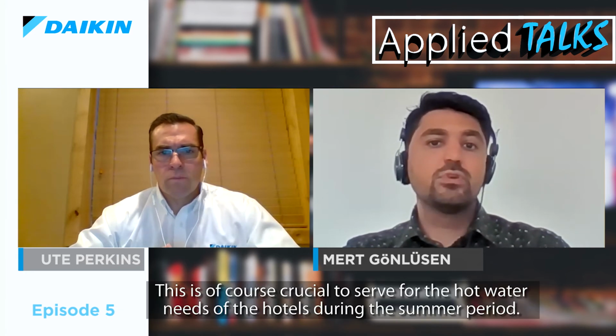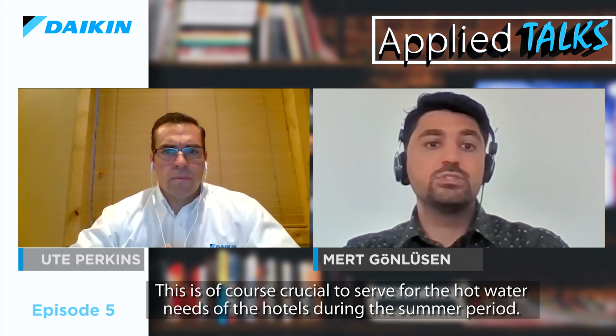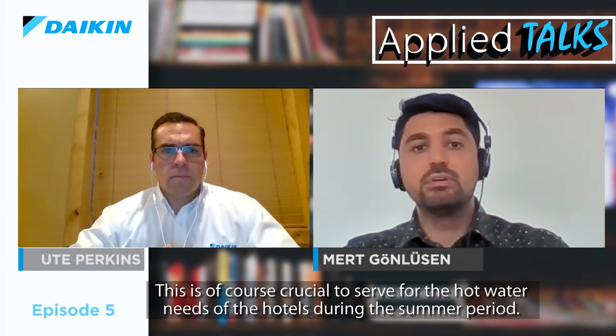Speaking about R-32 heat pumps specifically, we see it becoming a perfect solution especially for hotels, thanks to the new compressor's extended operating envelope. Now it's possible to have continuous heating operation, for example 60 degree condenser leaving water temperature at 35 degree ambient temperature. This is crucial to serve the hot water needs of hotels during the summer period.